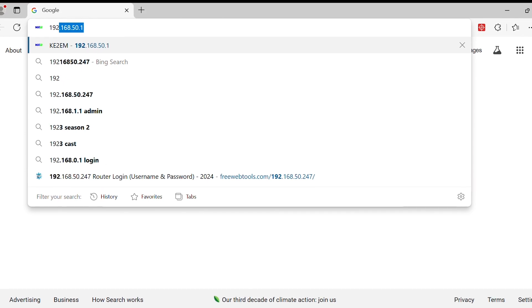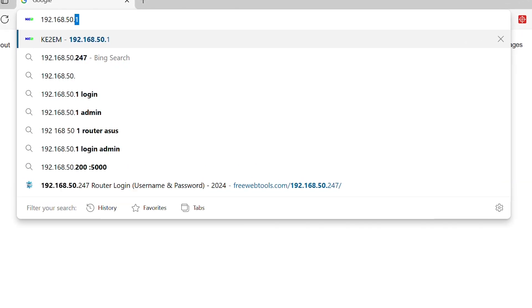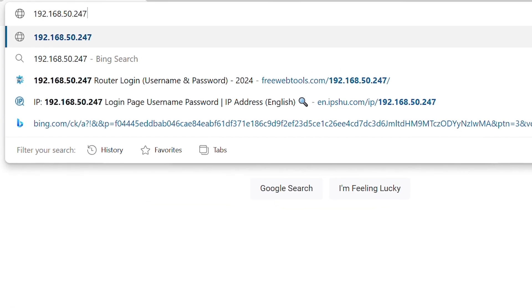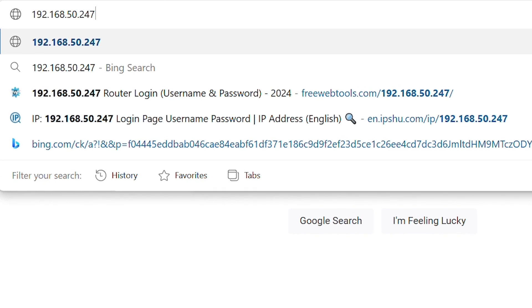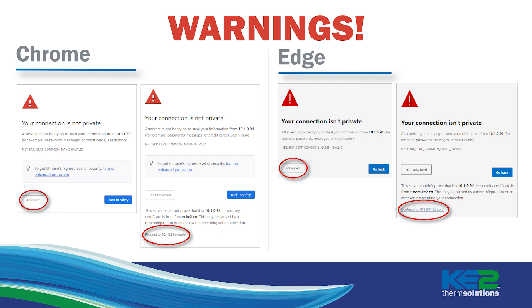This is important. Due to security improvements in version 5.0 and newer, your browser will likely display a privacy or security warning when first connecting to the controller via its IP address. Confirm the IP address of the controller is correct and then you can proceed. Depending on the browser, you'll click advanced or show details, then proceed to accept risk or continue to visit this website. This will bring you to the controller's web page. It's not generally advisable to click past this warning. However, proceeding past this warning when you're connecting to the controller is safe.